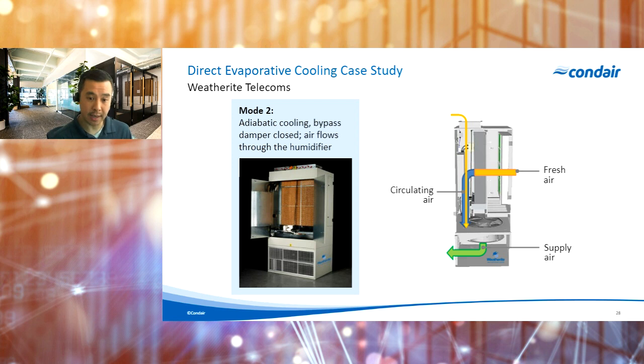As I mentioned, this is a fully recirculating unit on the evaporative module as well. In order to increase water efficiency and optimize the media life, we do have periodic drains on this system, and then we are recirculating that water that is not evaporated through that initial pass. So overall, you can see a very simple system, but it can yield some significant savings that we'll look at on the next slide.